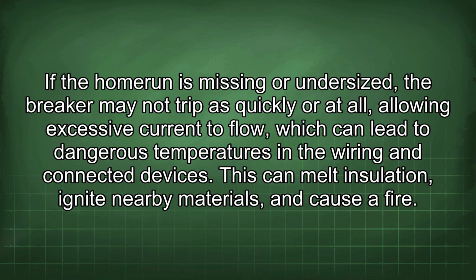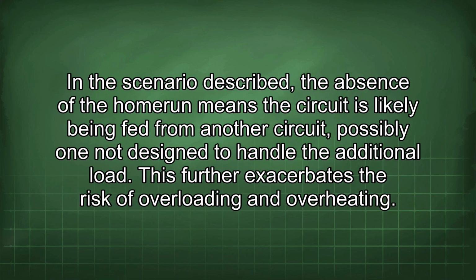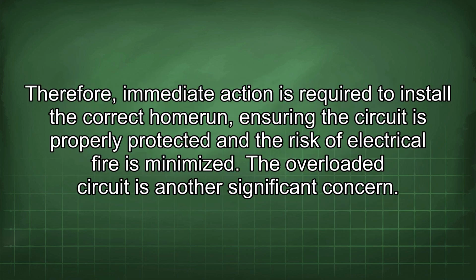If the home run is missing or undersized, the breaker may not trip as quickly or at all, allowing excessive current to flow, which can lead to dangerous temperatures in the wiring and connected devices. This can melt insulation, ignite nearby materials, and cause a fire. In the scenario described, the absence of the home run means the circuit is likely being fed from another circuit, possibly one not designed to handle the additional load. This further exacerbates the risk of overloading and overheating. Therefore, immediate action is required to install the correct home run, ensuring the circuit is properly protected and the risk of electrical fire is minimized.